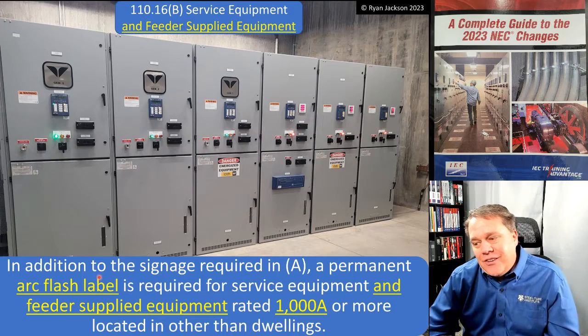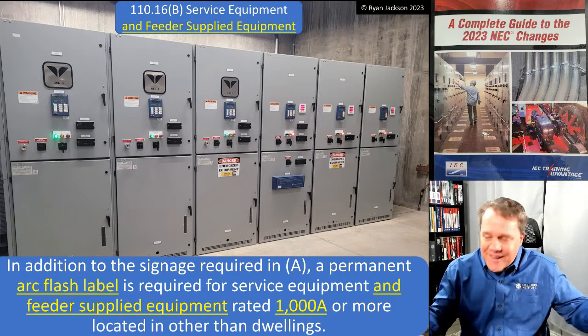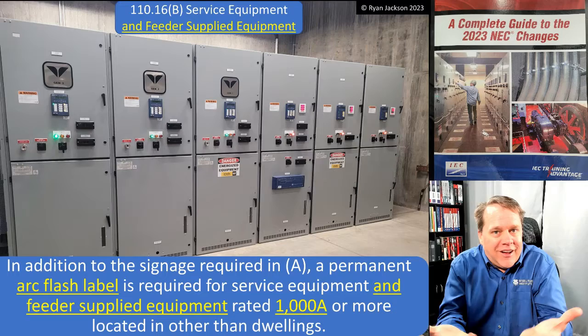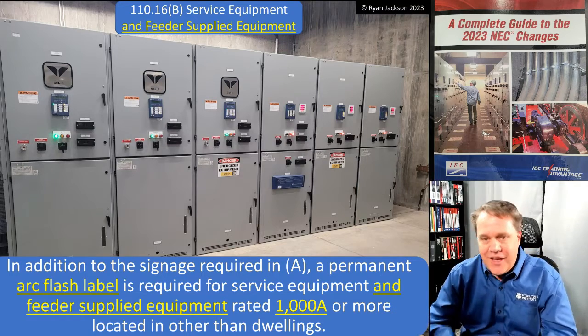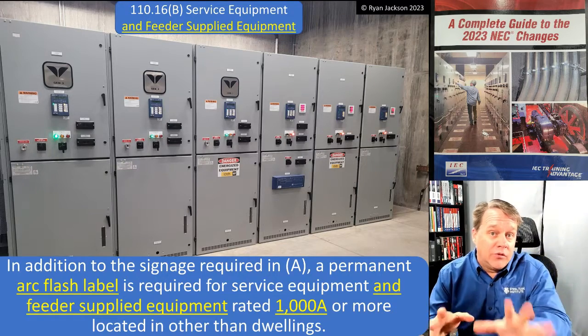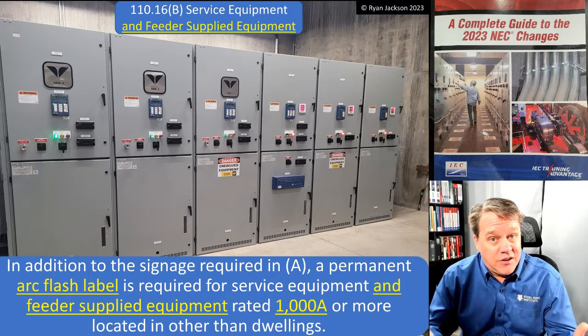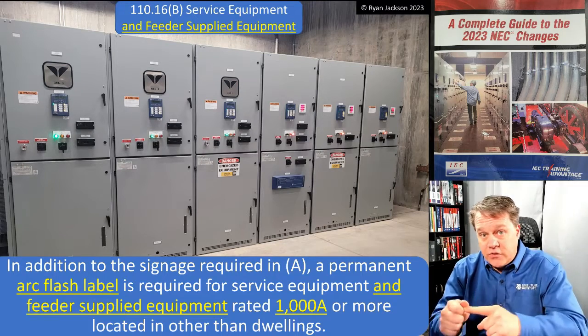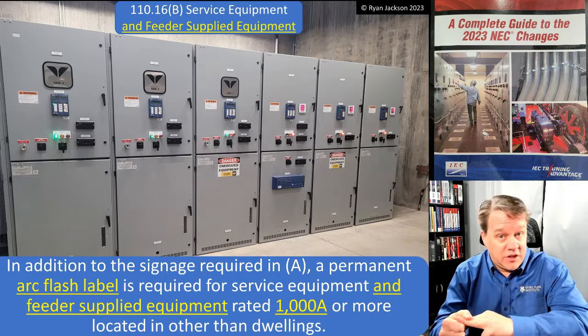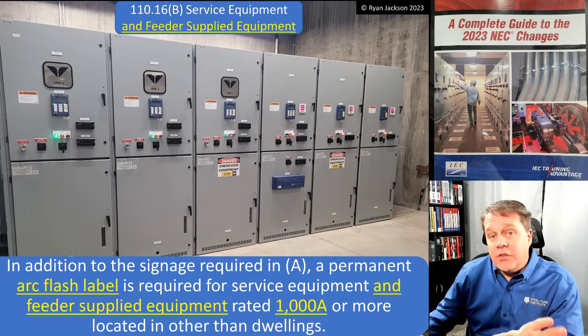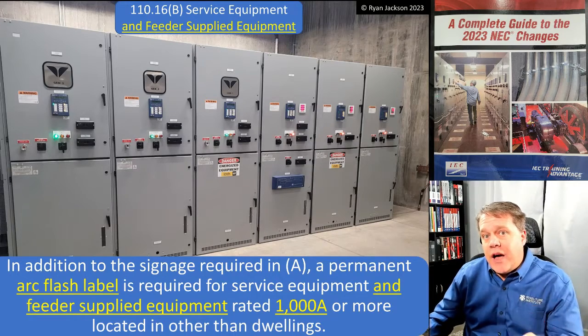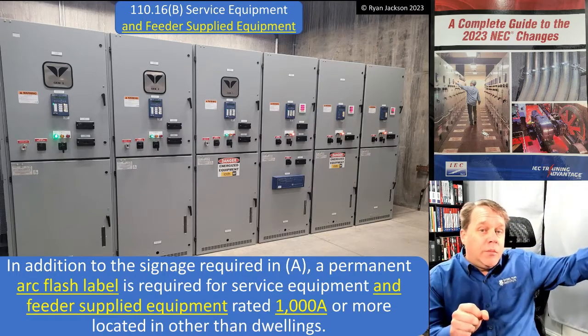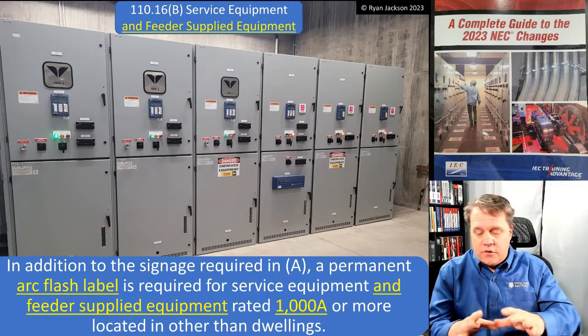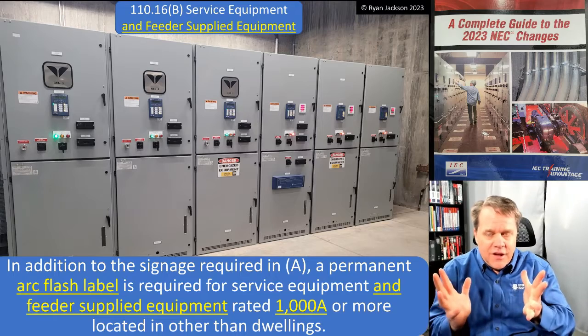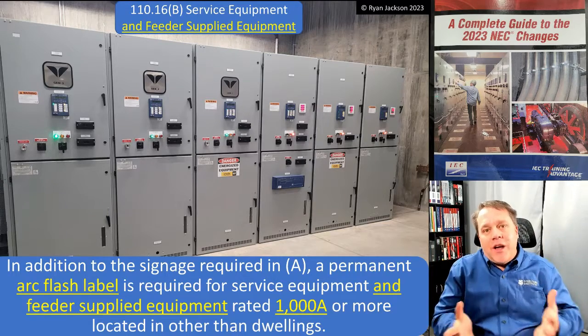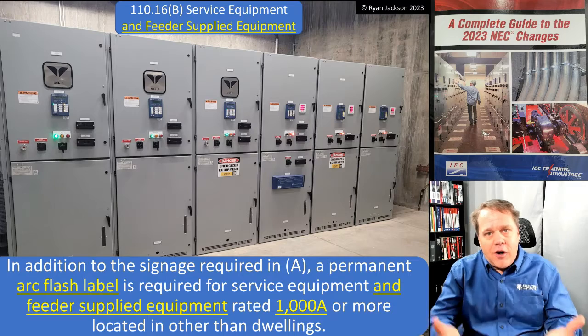But there was also kind of an oxymoron in the requirement, because it said, okay, yeah, those things, by the way, those are the three things that influence the incident energy. All right, how bad is the fireball? Depends. What's the voltage? What's the available fault current? What's the clearing time? Well, when we talk about the clearing time, we're talking about how fast is the breaker or fuse upstream of us open, right, to minimize the duration of the fault. Well, why would I write the clearing time on the service equipment?